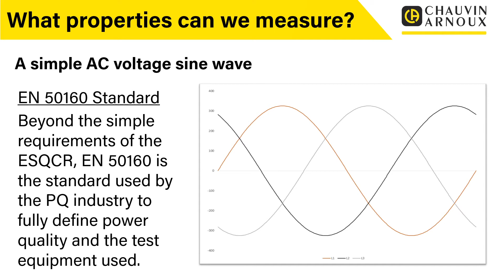So let's have a look at some of the anomalies, some of the things we might be looking for when we're doing power quality assessments. I talked about this perfect sine wave. We have this perfect vision of a sine wave, and actually quite often that changes. So we get these things called voltage sags and voltage swells. A voltage sag or swell is a short duration reduction or increase in the RMS voltage, often caused by changes in loading, for example, switching on or off large motors.